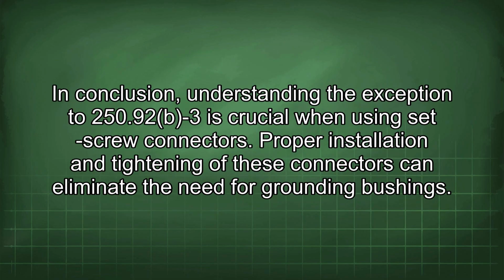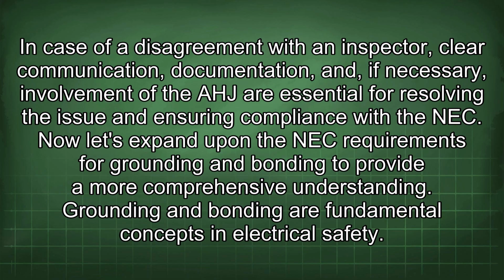In conclusion, understanding the exception to 250.92(b)-3 is crucial when using set screw connectors. Proper installation and tightening of these connectors can eliminate the need for grounding bushings. In case of a disagreement with an inspector, clear communication, documentation, and, if necessary, involvement of the AHJ are essential for resolving the issue and ensuring compliance with the NEC.